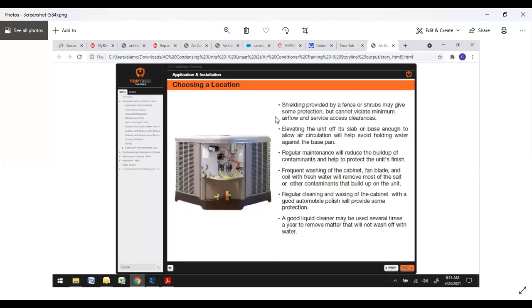Also, you can shield it with a fence or shrubs. It will give it some protection. There again, don't violate the minimum airflow and service clearances. I've had to actually climb on top of them in the past, and service units kind of hanging upside down. It's not easy other than for just basic service, and it will affect operation if it can't breathe. In some cases, you have to elevate the unit off its slab or base to allow air circulation to avoid holding water in the base pan.